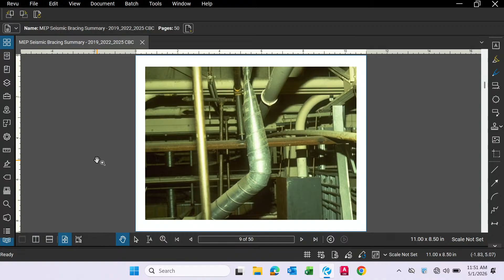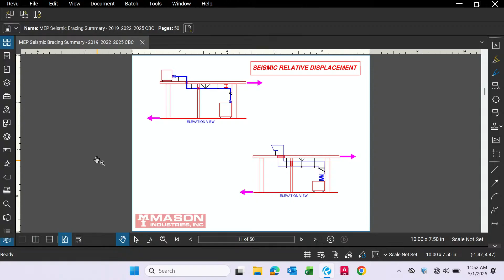Designing for relative displacement. This is a big one, and it's part of the code. In the later code cycles, they really emphasized, put a lot of emphasis on this seismic relative displacement. As I mentioned earlier, in a seismic event, the floor could move in one direction, and the ceiling above it could move in the opposite direction. And if you're not careful, the connection at the equipment can get ripped apart.